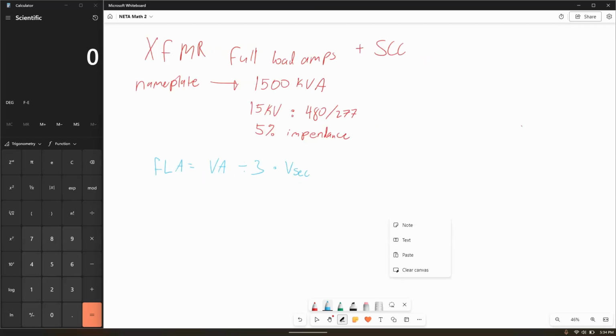So in this example, we've got 1500 kVA, so that is 1,500,000 volt amps, and then we're going to divide that by 3 multiplied by our secondary voltage. Now our secondary voltage in this case, I've got a phase to phase and a phase to neutral voltage. I want the phase to neutral voltage. So if you only had the phase to phase voltage, you would divide that by the square root of 3. So this is 277. So this would also equal 500,000 VA per phase. And then we divide that by the phase to neutral voltage.